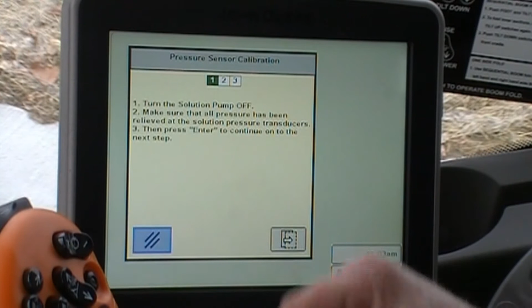Below that is a solution pump calibration. This is just made for if a major component has ever been replaced on the machine, or something has failed, a control valve, anything like that - we will go into calibrate the solution pump.